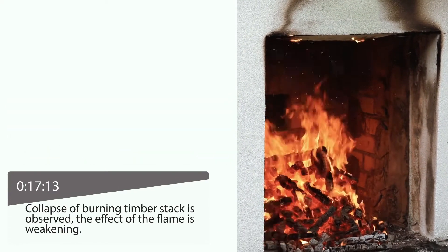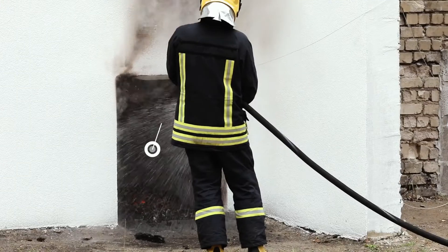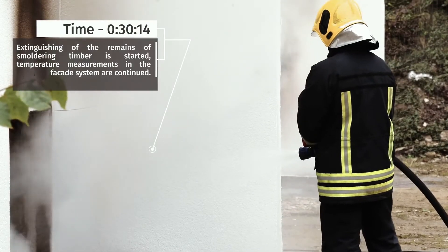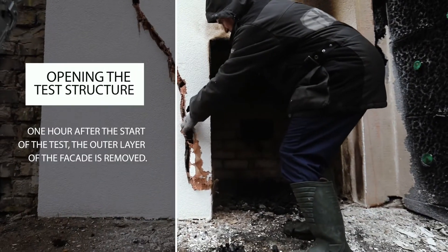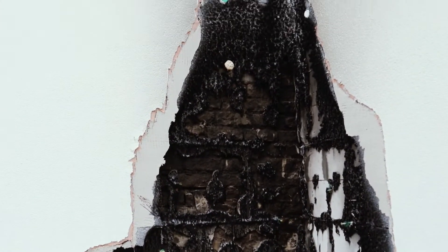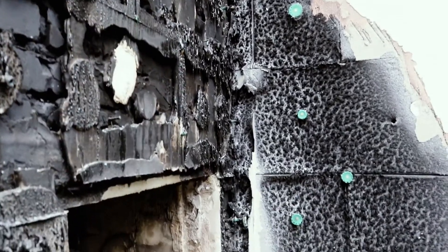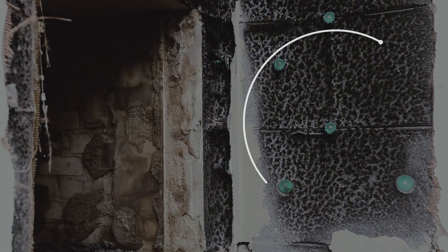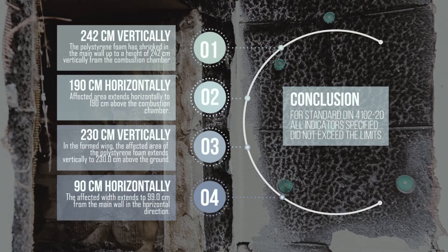After 17 minutes, the collapse of the timber stack is observed, causing the temperature to drop. After 30 minutes, extinguishing of the timber remains is started. One hour after the start of the test, the outer layer of the facade is removed. It is found that the polystyrene foam has shrunk in the main wall up to a height of 242 cm vertically from the combustion chamber, while horizontally the affected area extends to 190 cm. In the formed wing, the affected area extends vertically to 230 cm from the ground and horizontally to 90 cm from the main wall.